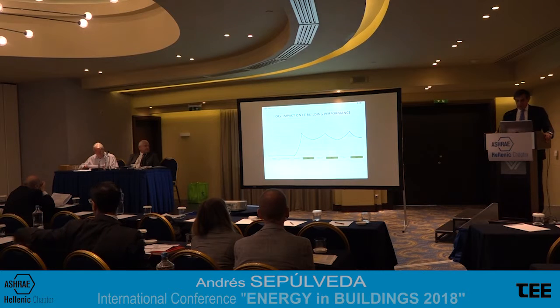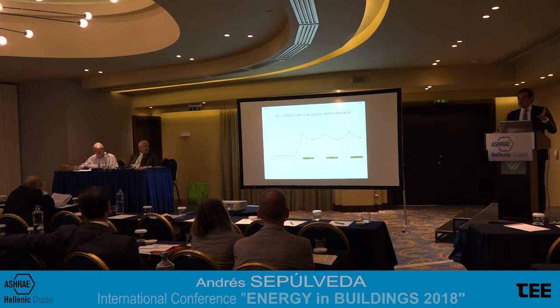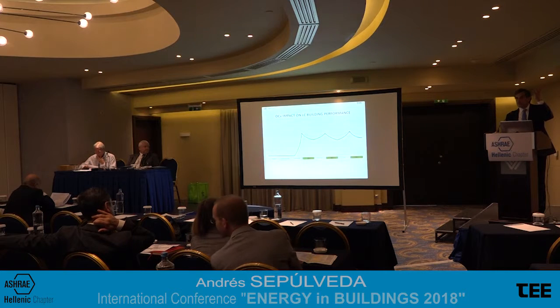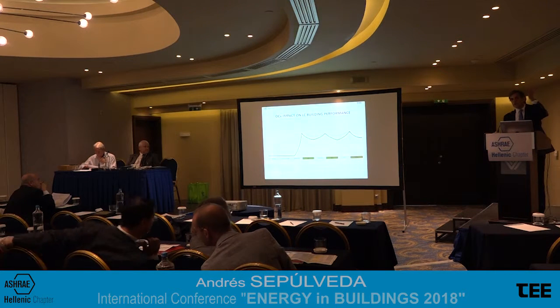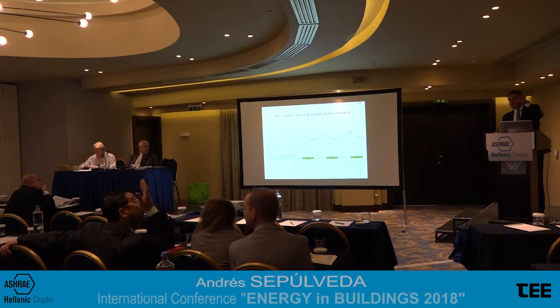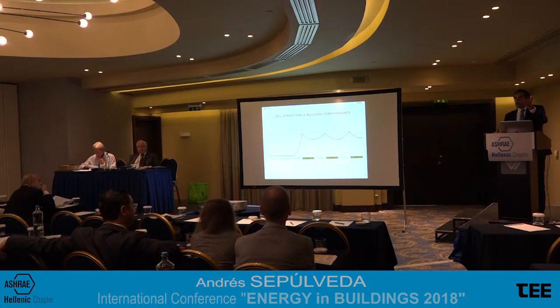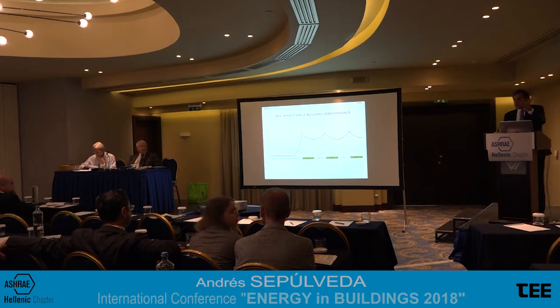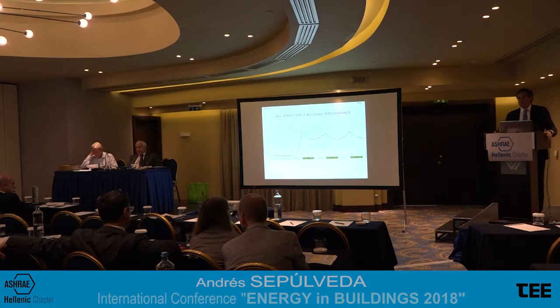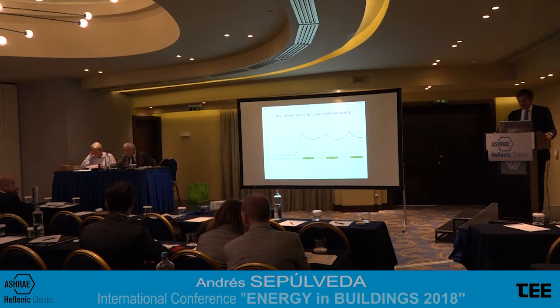And I must say it's very good to do that because, after a commissioning process, the building is delivered at the highest energy performance. But this performance deteriorates during the life of the building. If we have a continuous commissioning program, the effort required to fine-tune and adjust the building will be less than if nothing is done and we let the building just lose efficiency and performance.